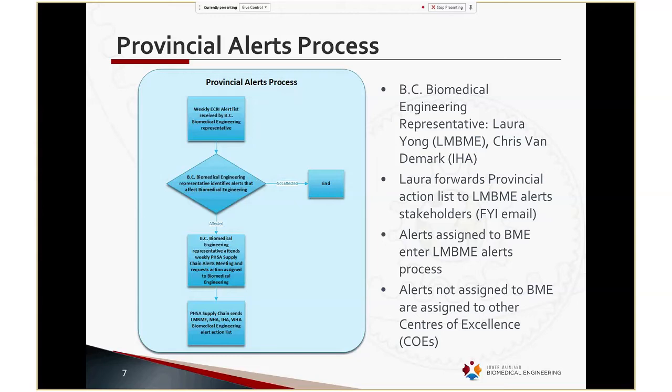So basically what happens during this call is PHSA supply chain runs through every single alert on that ECRI list, and it gets assigned to one or more centers of excellence. So what Laura and Chris will do is they've already performed the first pass of this list, so they have an idea of which alerts should be actioned to biomedical engineering because they affect electromedical devices. And during the call, they'll speak up, and whenever one of those alerts is mentioned, they'll say, yep, that's likely related to biomed.